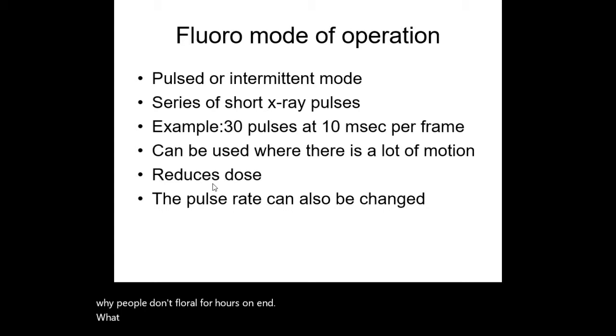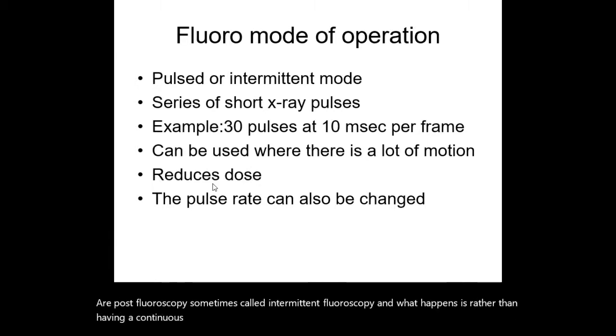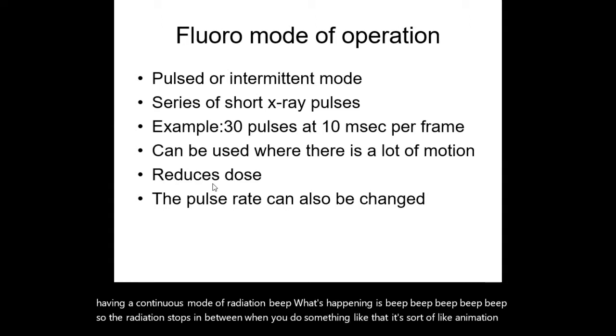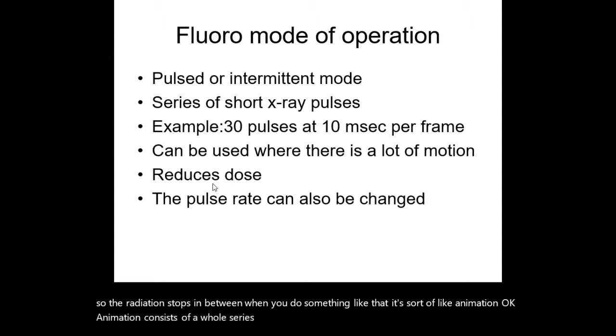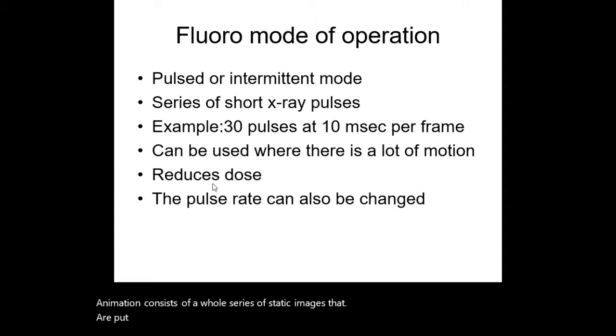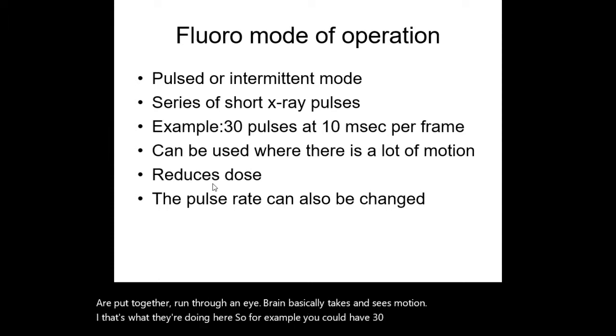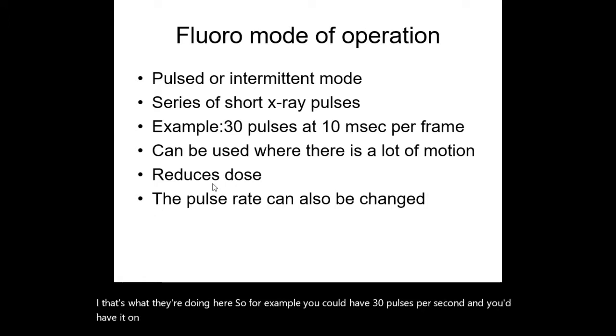What is used mostly today is pulsed fluoroscopy, sometimes called intermittent fluoroscopy. Rather than having a continuous mode of radiation, what's happening is beep, beep, beep, beep, beep. So the radiation stops in between. When you do something like that, it's sort of like animation. Animation consists of a whole series of static images that are put together and run through, and our brain takes that and sees motion. That's what they're doing here. So, for example, you could have 30 pulses per second, and you'd have it on, then off, on, then off. And the advantage, again, I repeat, is a reduction in the radiation dose.